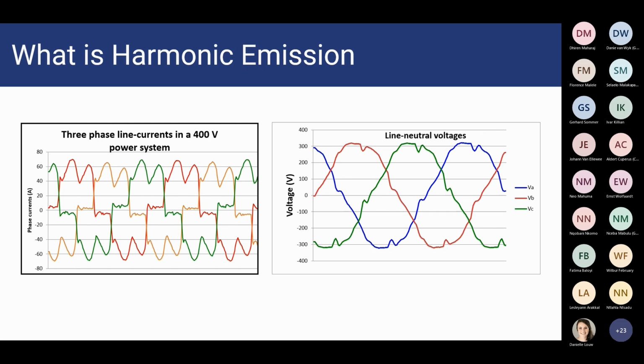Here's an example of a load on an LV system drawing distorted currents. You can see it looks like 6 pulse rectifiers, and an example of how that load current affects your line voltages at the point of measurement on LV. So we can see how distorted the waveform becomes.